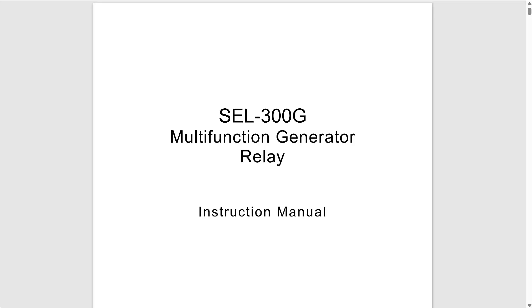The SEL 300G relay implements the loss of field protection by measuring the positive sequence impedance at the generator terminals, and it does this by using two zones of mho elements which we can set with a positive or negative offset. For this video we're going to be focusing on the negative offset scheme, which is the most commonly used one.